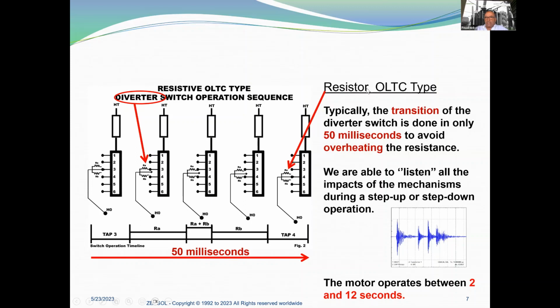Typically for the resistor OLTC type, the transition of the diverter switch is done in only 50 milliseconds to avoid overheating the resistance. This value is important because it helps you check if the vibration that you can see here is done in 50 milliseconds. So we are able to listen to all the impacts of the mechanism during a step up or step down operation. Another important parameter is that the motor operates between 2 and 12 seconds. So we must find these two pieces of information in our Vibro-Acoustic signature.